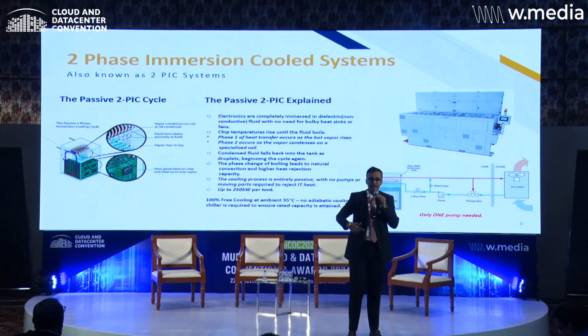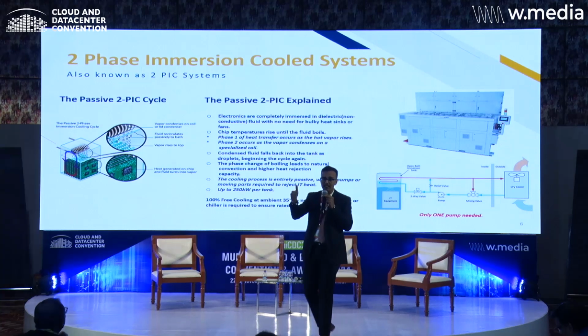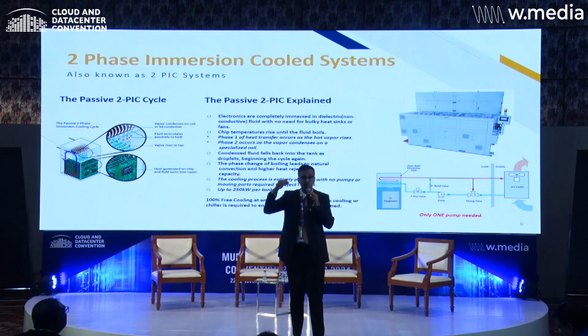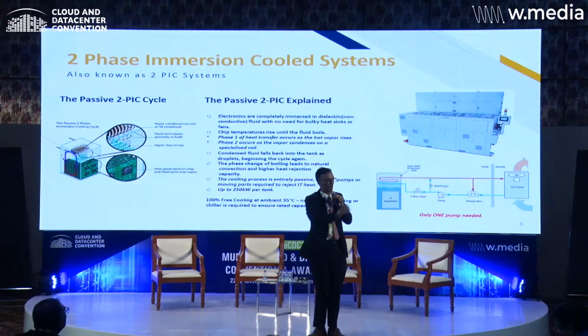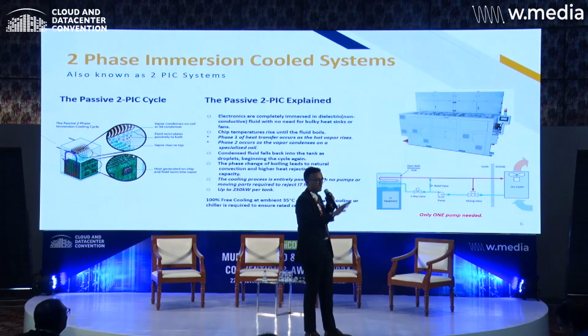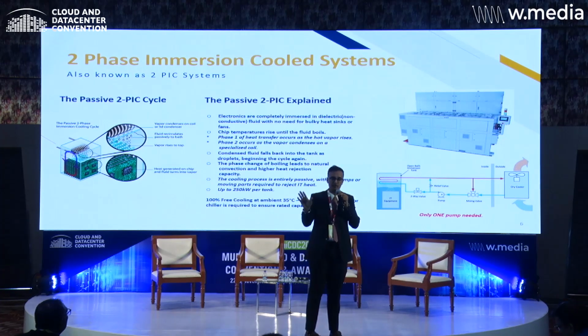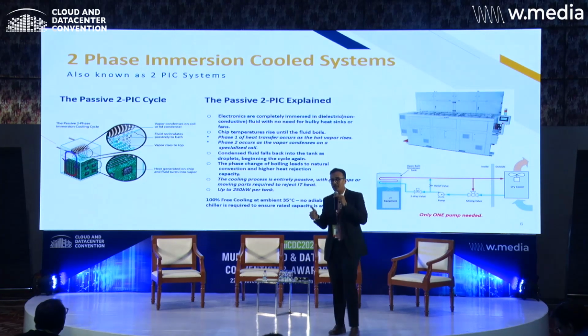So the entire passive cooling that is happening creates such efficiency that the electromechanical PUE of this system, up to 250 kilowatts per rack, is only 1.04. That is 50% savings in PUE, which is 33% savings in OPEX every year for a data center provider who has an OPEX cost of multiple millions of dollars. Very simple system: just a tank, liquid, one pump to push in the water, and a dry cooler. Nothing else. No false floor, no chillers. That makes your data center design much easier.